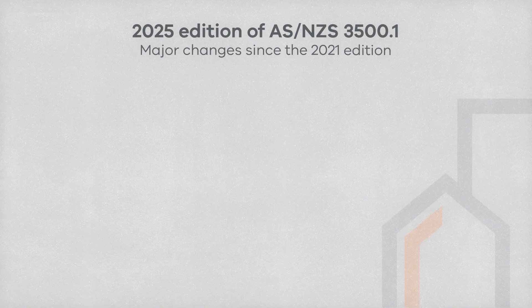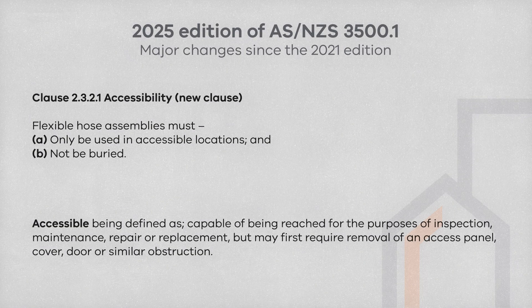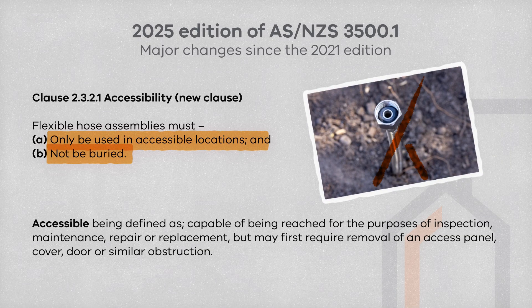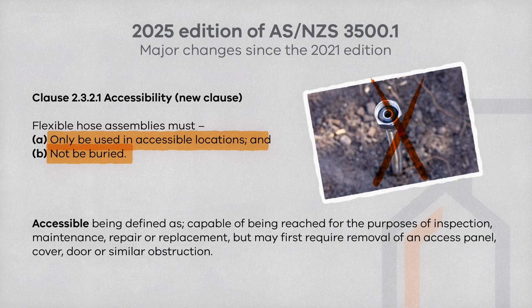Clause 2.3.2.1 goes over the accessibility requirements: flexible hose assemblies are only to be used in accessible locations and must not be buried. The term 'accessible' is defined in the standard as capable of being reached for the purposes of inspection, maintenance, repair or replacement, but may first require removal of an access panel, cover, door or similar obstruction.